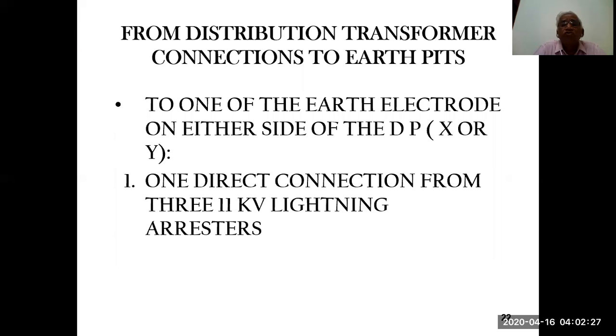From the distribution transformer, connections go to the earth pits: to one of the earth electrodes on either side of the DP, X or Y, you can connect it, and one direct connection from the three 11 kV lightning arresters. All the lightning arresters have a strip at the bottom already given by the manufacturer. That strip you have to extend with the same size or a bigger size of GI strip and connect directly to the electrode. Don't connect it to the transformer or to the structure. It should be taken down. At the bottom you have a third earth electrode available, and give a connection to that.